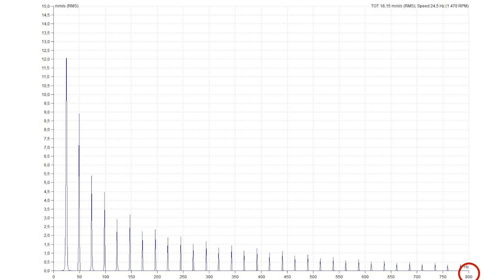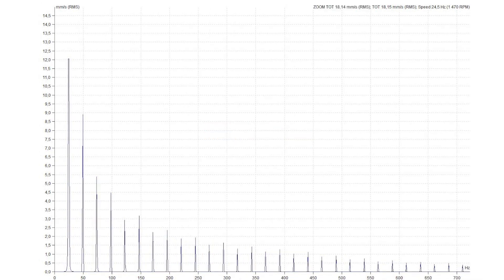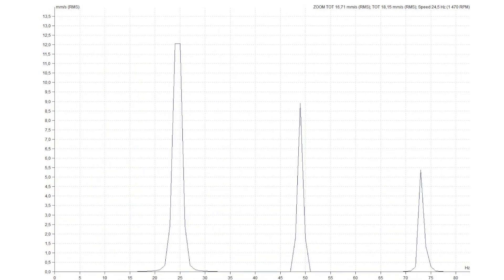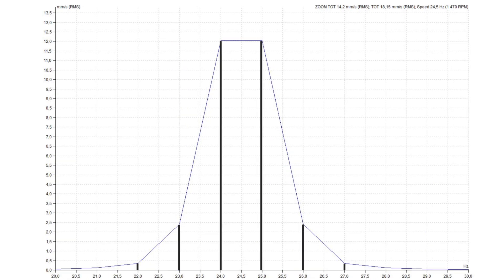Spectrum has a frequency range and contains a number of lines. Spectrum has a resolution, which is defined as the frequency interval between lines. The spectrum lines are only on a limited number of frequencies. When the resolution is 1 Hz, then we get lines on, for example, 22 Hz, 23, 24, 25, 26 Hz and so on.